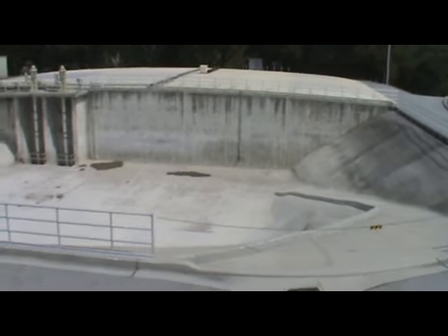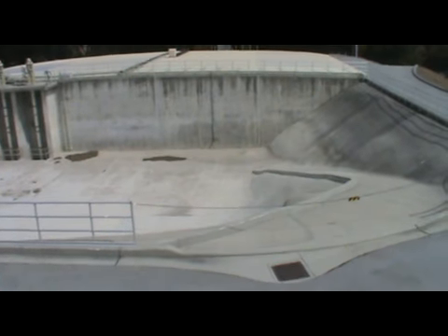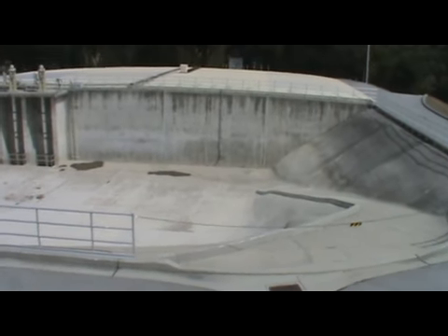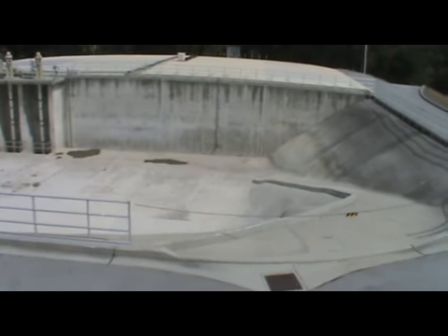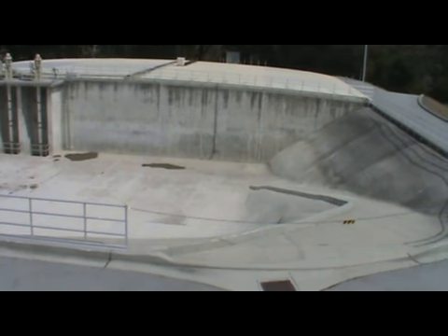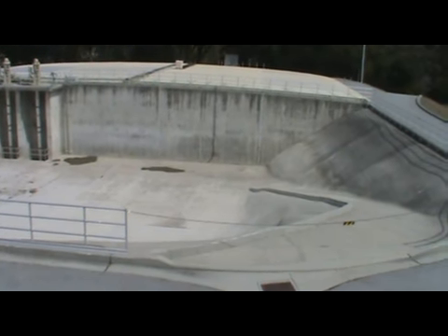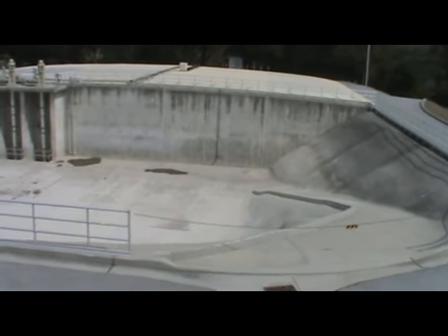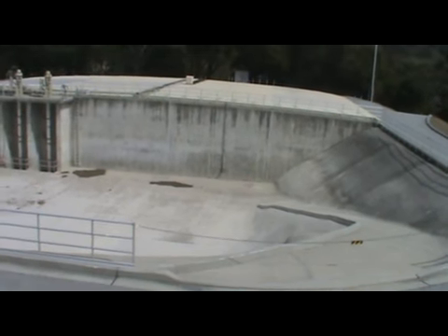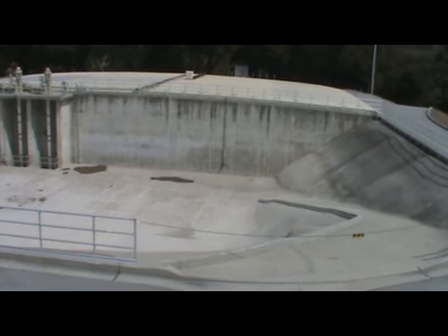Now there's this great thing in front of me that looks like it'd be skateboarder's paradise. If you're asking what that is, that's what they call an off-spec basin. If for some reason turbidity starts to rise in the plant or effluent chlorine looks like it's going to go low, this is a catch-all. Instead of directing water into the clear well, they can direct the water into this off-spec basin while everything gets caught back on track.